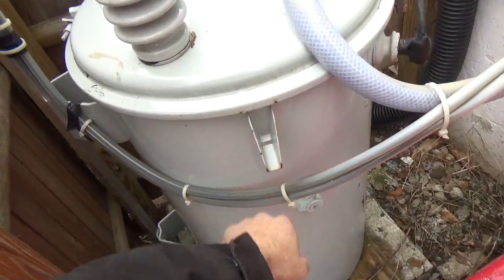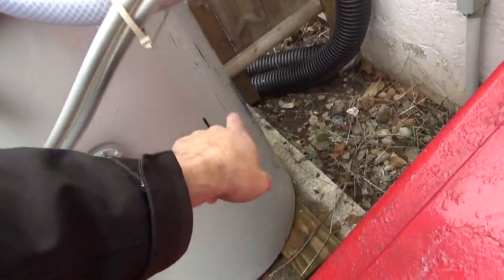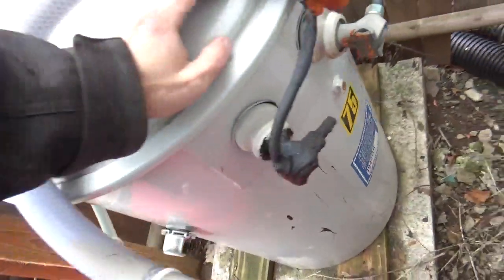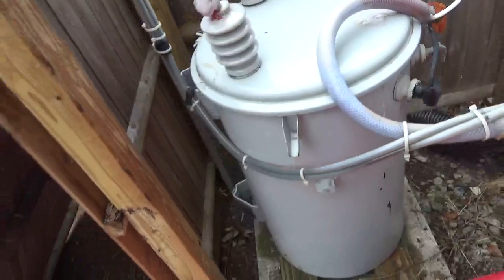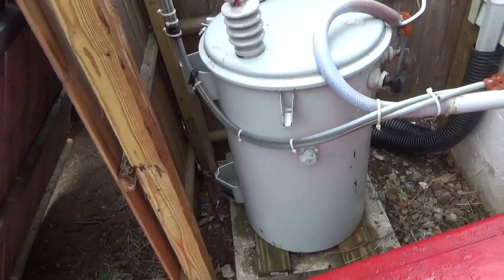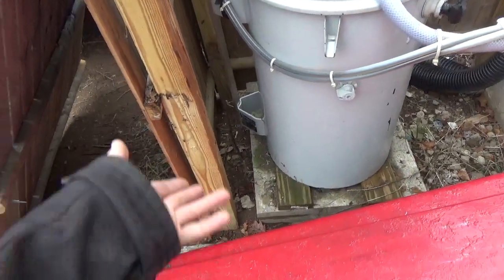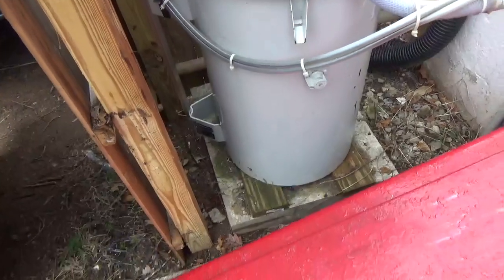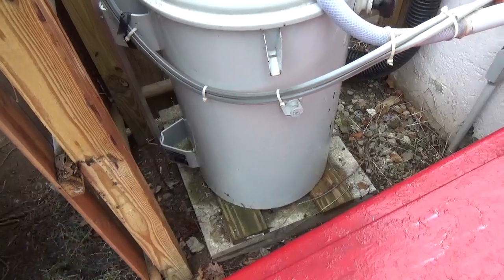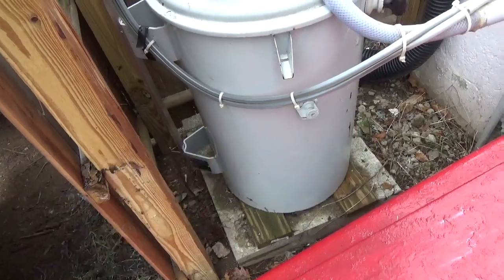It's starting to get a little rust on it, and that's the liquid electrical tape. You can see the 75 kVA rating — this has no PCBs in it, and it has a pressure vent on the other side. I got it up off the concrete pad — I poured that myself, go crazy with everything: it has rebar in it, and it's elevated to keep it out of the water so it won't rot underneath.